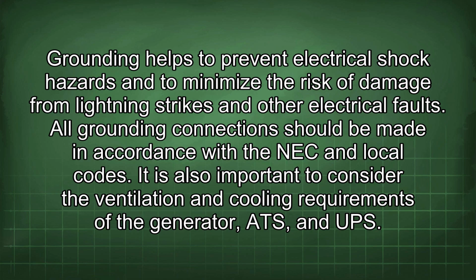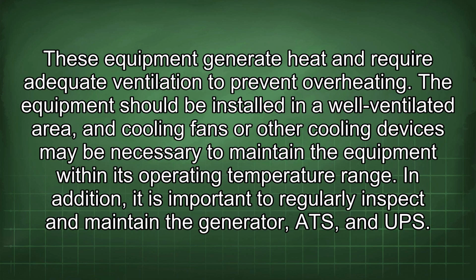Grounding helps to prevent electrical shock hazards and to minimize the risk of damage from lightning strikes and other electrical faults. All grounding connections should be made in accordance with the NEC and local codes. It is also important to consider the ventilation and cooling requirements of the generator, ATS, and UPS. This equipment generates heat and requires adequate ventilation to prevent overheating. The equipment should be installed in a well-ventilated area, and cooling fans or other cooling devices may be necessary to maintain the equipment within its operating temperature range.